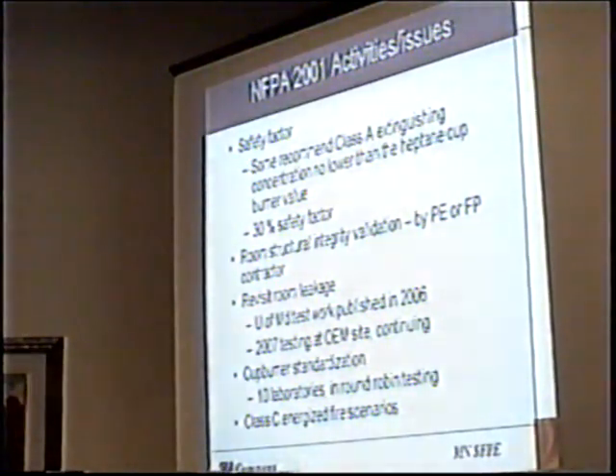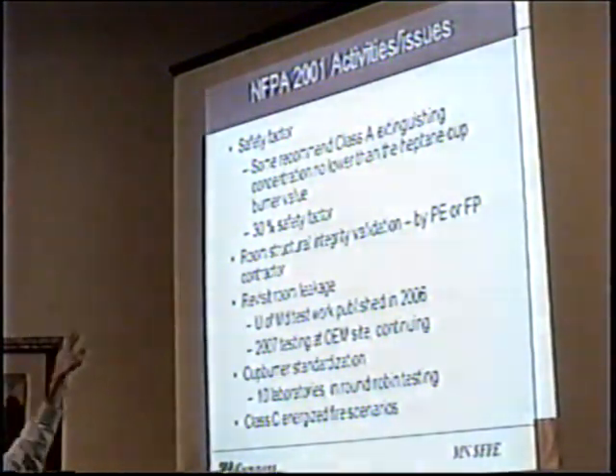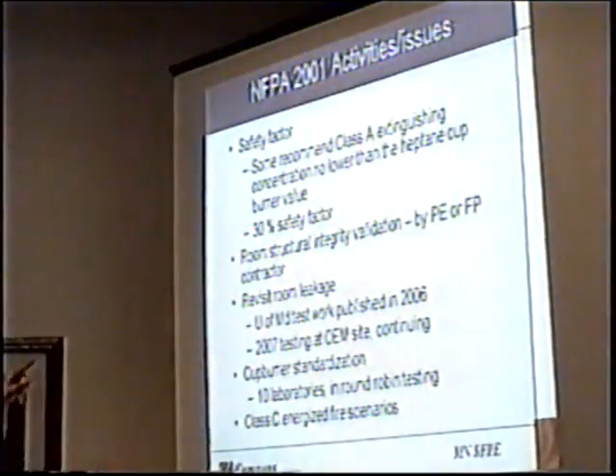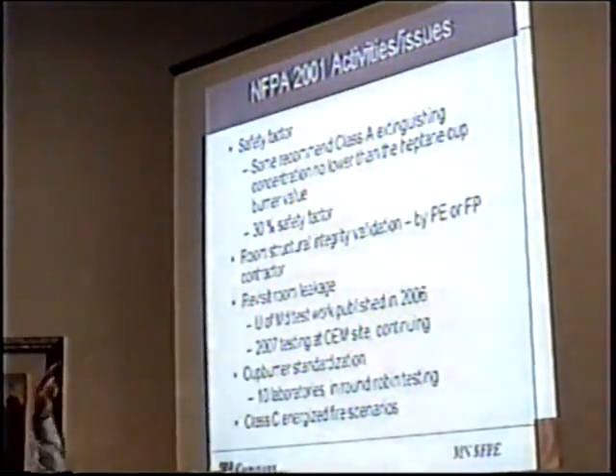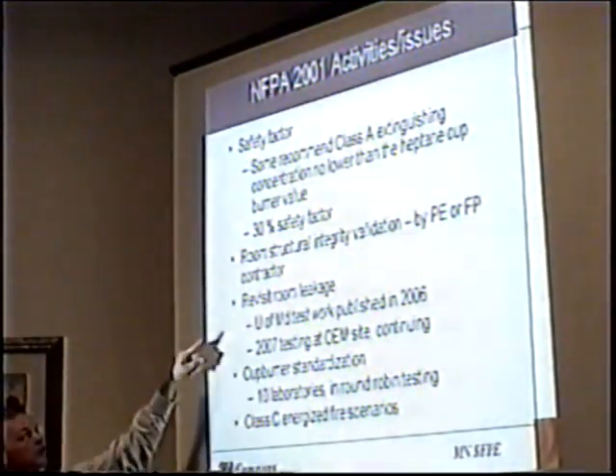Room structural integrity validation. Should that be done by the professional engineer, or should it be done by you, the fire protection installer? Should you be responsible for that, or should that be from the PE? Responsible for the testing, they're responsible for... Yeah, that's right. So there's a real debate going on about that. That gets into the PE licensing versus the NICET licensing and so forth. There's a lot of debate going on with that. Right now, going into the standard, there's a requirement that the fire protection contractor is going to be required to validate something he has absolutely nothing to do with.